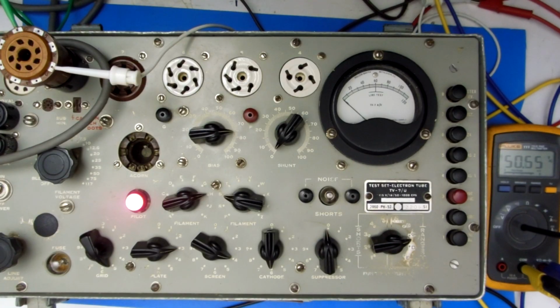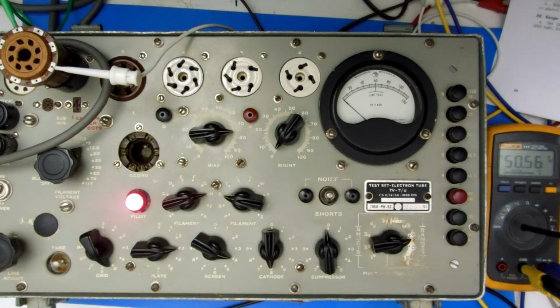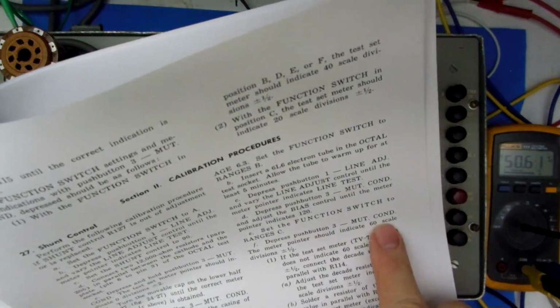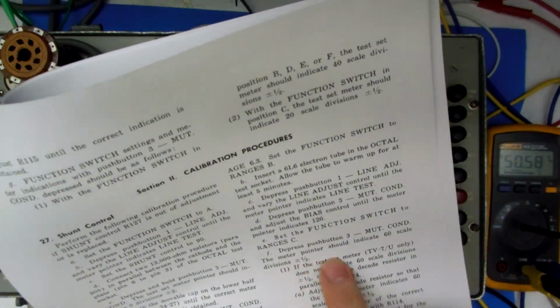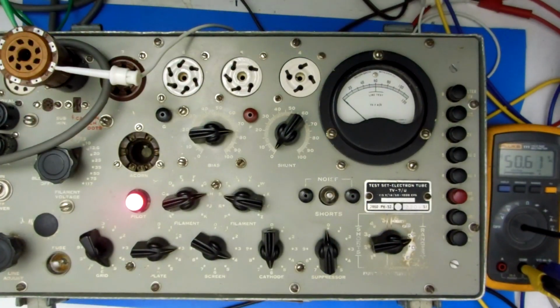And that does it. Those are the basic tests for this document. If you come out close or within spec of what they call out, because right here they call out 60 scale divisions plus or minus 1/2, if you're pretty close to that in all the different paragraphs, it's in spec.